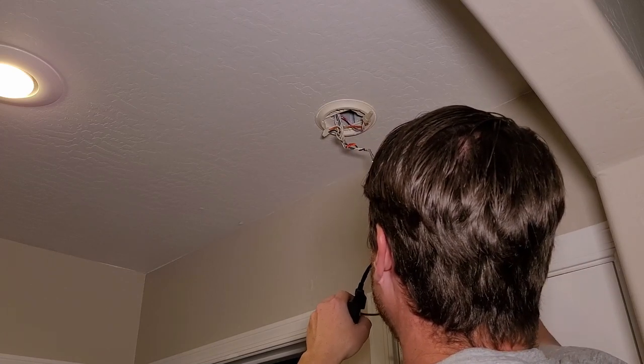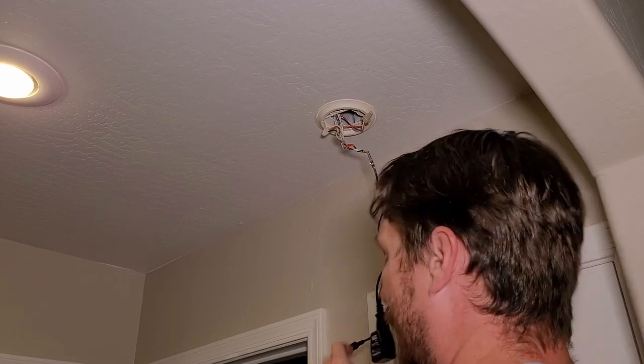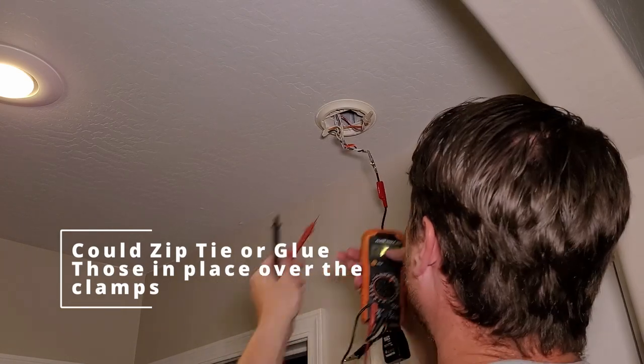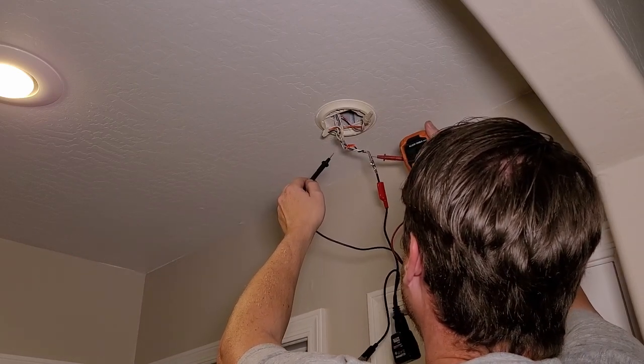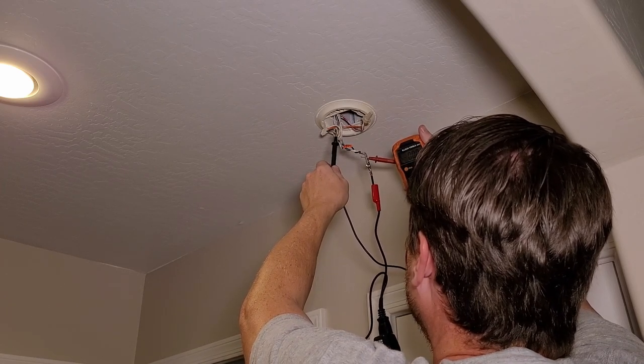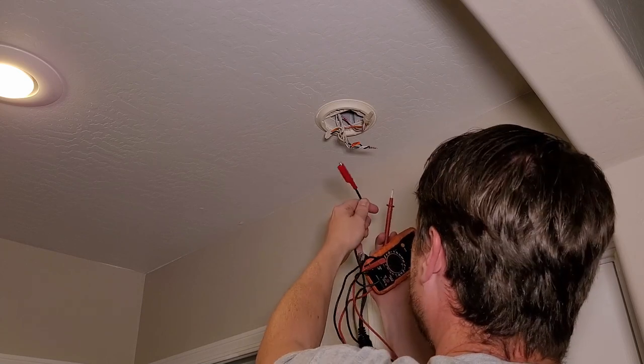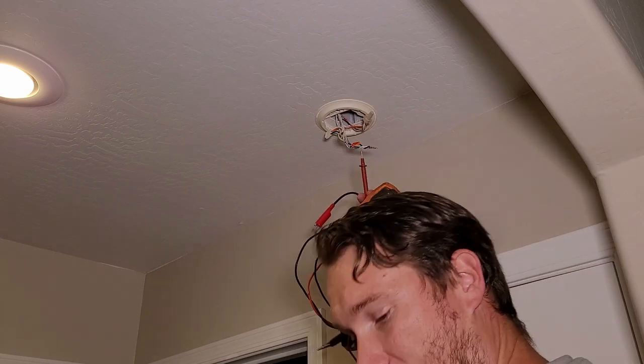See that? The little cover slipped off of that. And if that's live, it can get knocked out pretty good. Let's go ahead and take our multimeter — that's pretty bad. They should have done something to stop that. See how that thing slipped down? How fun would that be if that was live? You can only find the circuit breaker if it's live. It's a dead circuit, so we know we're okay. Look at this stupid cover sliding off — be careful of that, guys. That could be a real bad thing. And if you get shocked, you fall off the ladder, you break your neck, you're done.